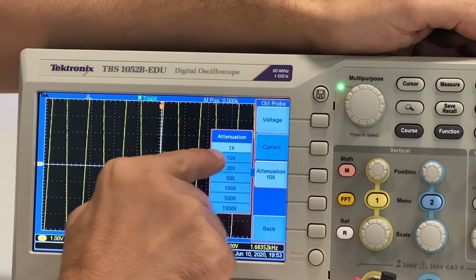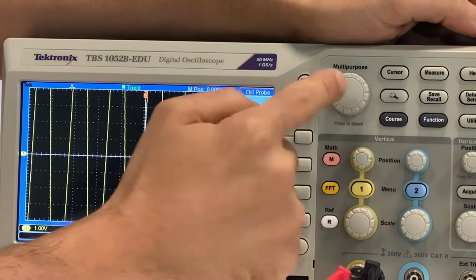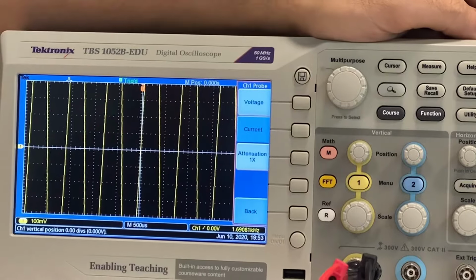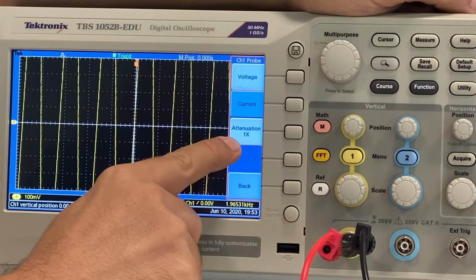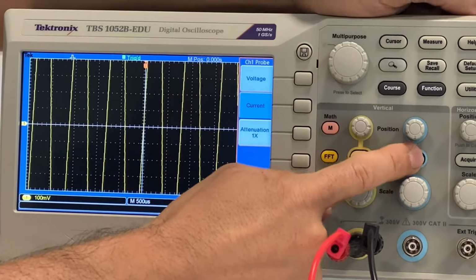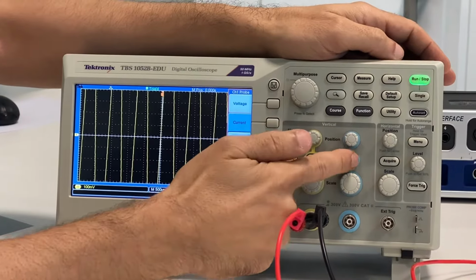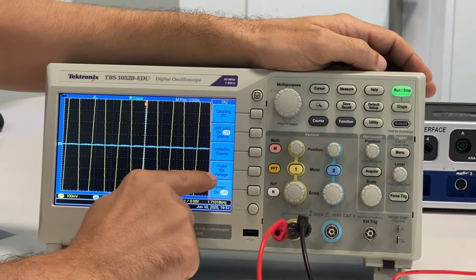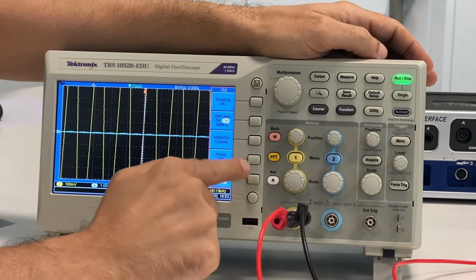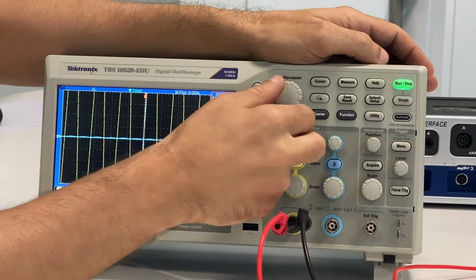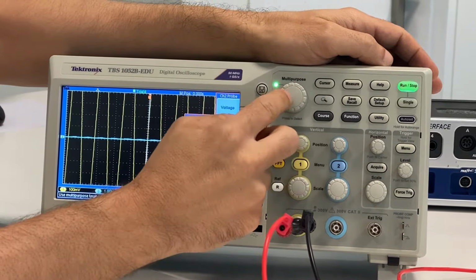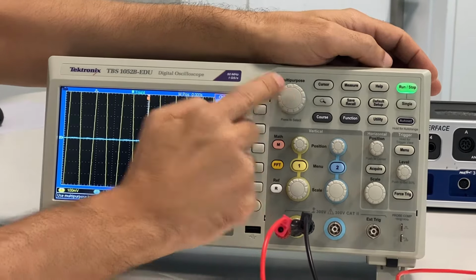So I want the 1x. So I have the 1x highlighted, and I'm going to press the same knob. Now the attenuation changed to 1x, okay? If you are using the two channels, you have to do the same setting for the other channel as well. So you press on channel 2 and you have to change it again. So let me redo it quickly. This one, and then attenuation. Then you select 1x and press.